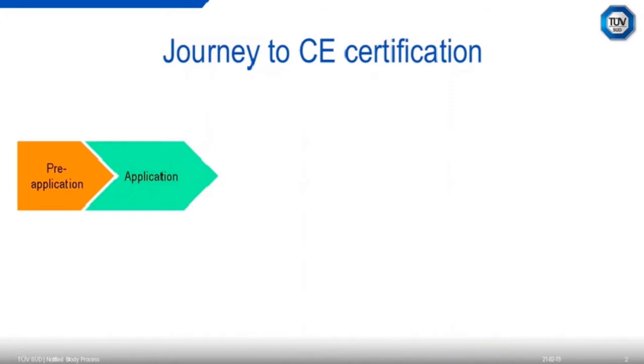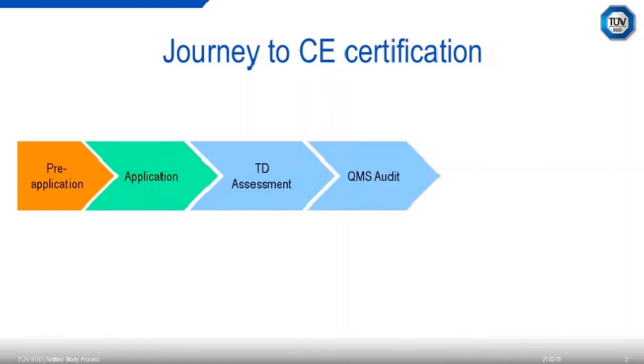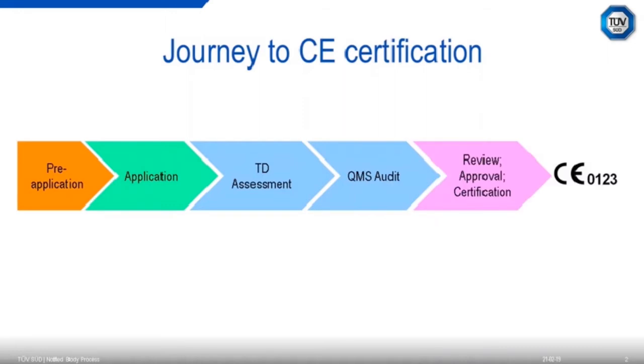So as a manufacturer, you have a journey to CE certification that always will start with a pre-application. This is a new requirement of the regulation, and we'll explain what the purpose of that pre-application is. We will then move to the full application process. And then finally, when that process has been approved, the rest is what you're aware of: the technical documentation assessment, the QMS audit for your company. And then finally, the notified body would do the review, the approval, and then the certification.